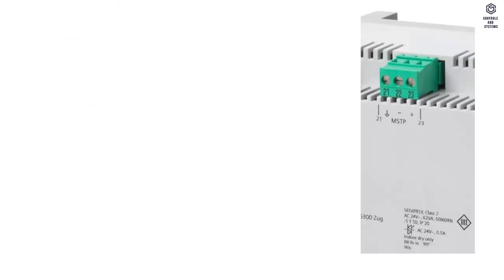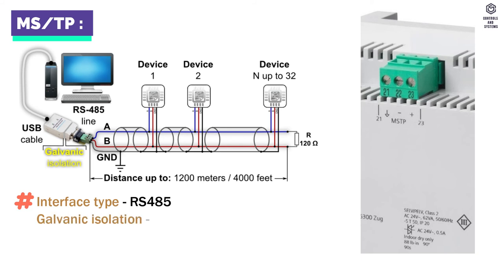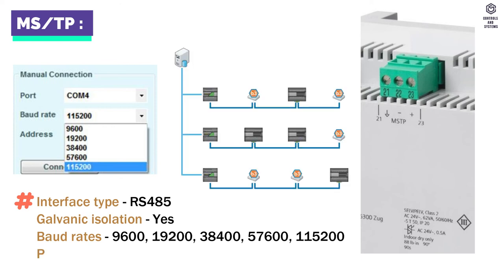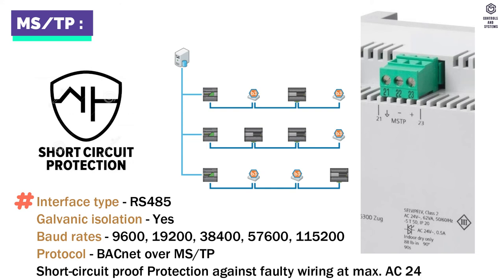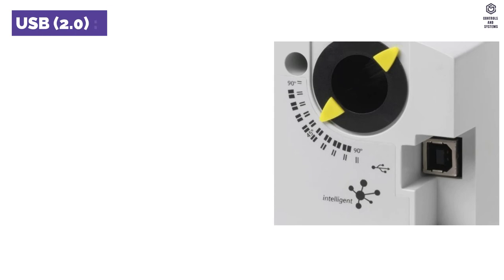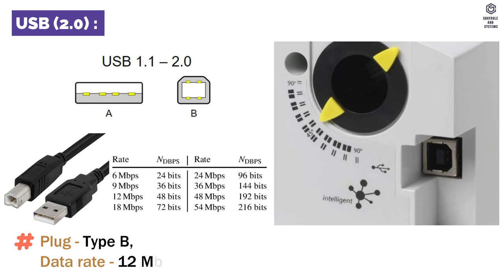Interfaces — MS-TP: interface type is RS-485, galvanic isolation is available. Baud rates are shown in the table. Protocol is BACnet over MS-TP. Short-circuit proof protection against faulty wiring at maximum AC 24V. USB 2.0: plug is type B, data rate is 12 Mbps.